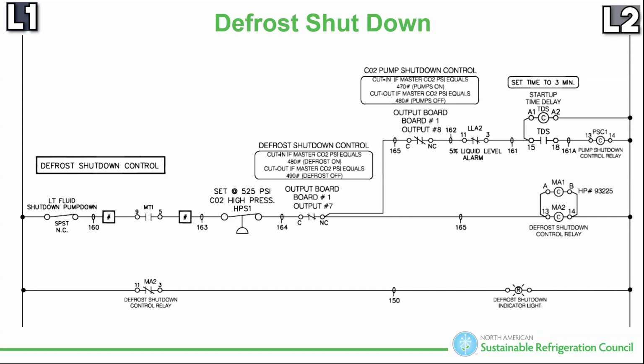So I always keep that in mind and try to use one hand when I can. If I tie that black lead to T2, L2, then I can put my magnet on my brand new Fieldpiece meter and go. So PSC1's not working, the pumps are not, so let's do this. I just tied my lead to T2, L2.